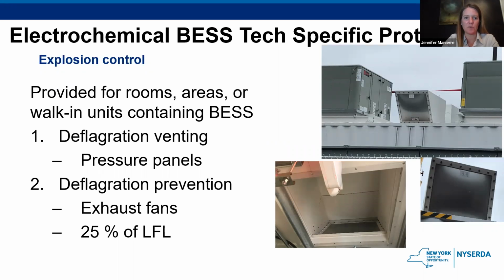Explosion control is always a fun one. This is one where I pointed out that even though lithium ion batteries don't need the exhaust ventilation by default, they do require explosion control because they can off gas in the event of an incident where they're overheating or catching fire, right? So they need to have deflagration venting, which is like pressure panels. Basically, should an explosion occur, those panels will open and direct the explosion up and away versus allowing the explosion to come where you don't want it to go, like out the front door of a system where there might be a person standing. So those panels direct the explosion where it's safe for folks.